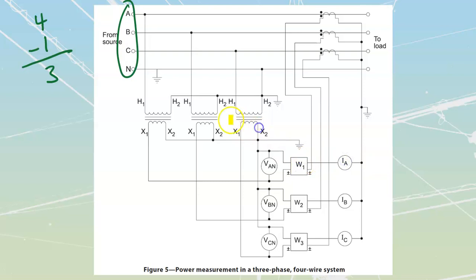If we take a look, I see there's 3 PTs across here, and I see there's 3 CTs across here. So PT and CT, PT and CT, PT and CT means we have 3 watt elements for this 4-wire system - 3 watt elements.